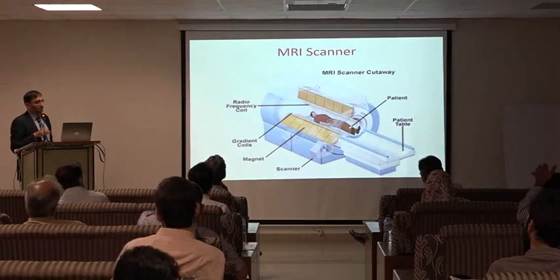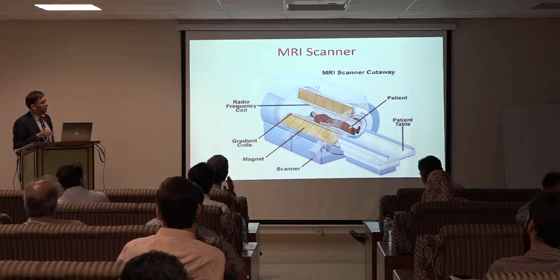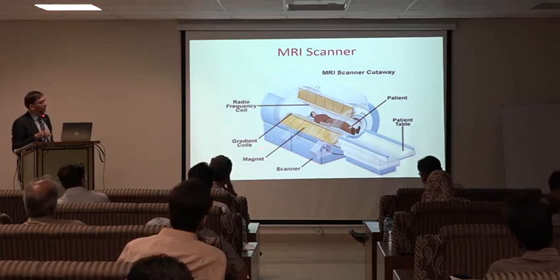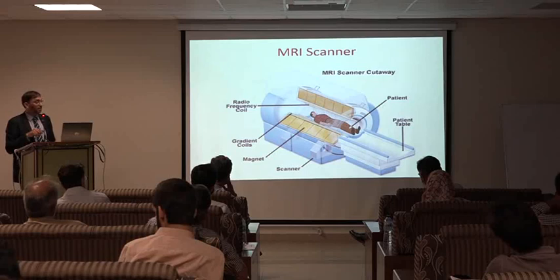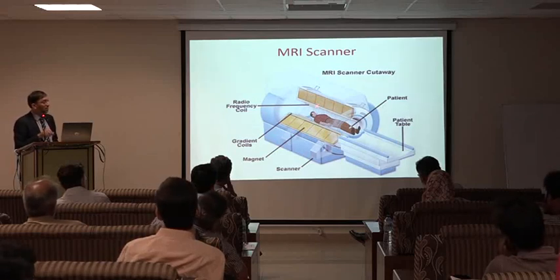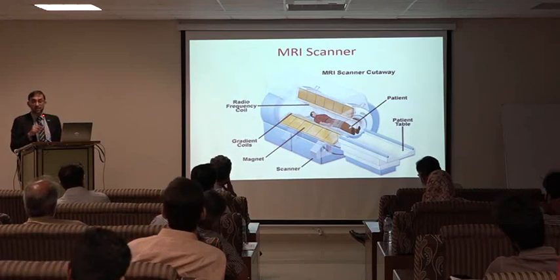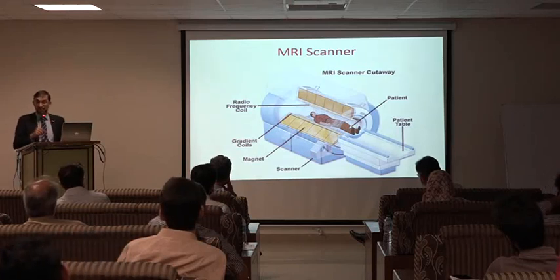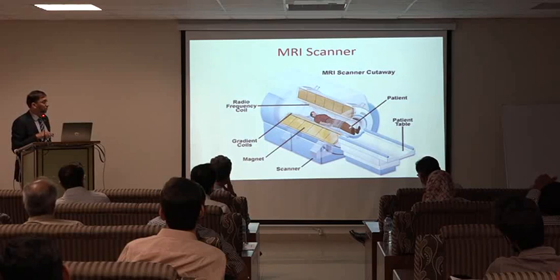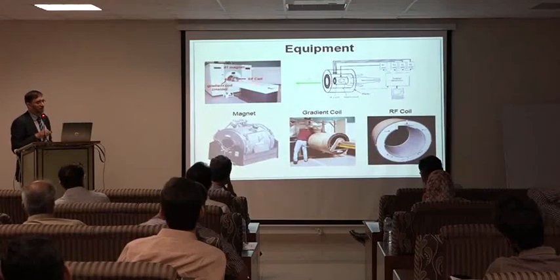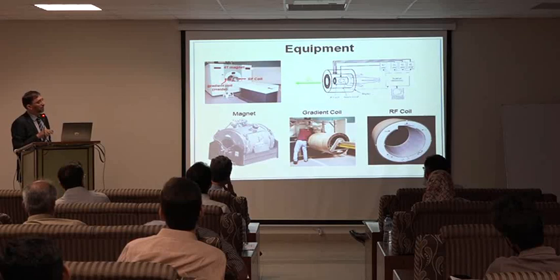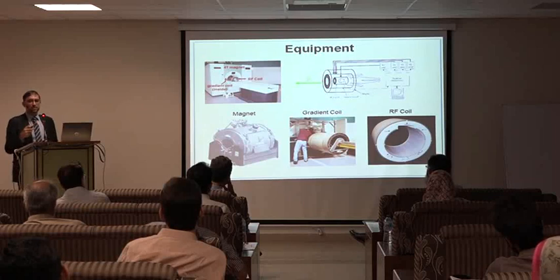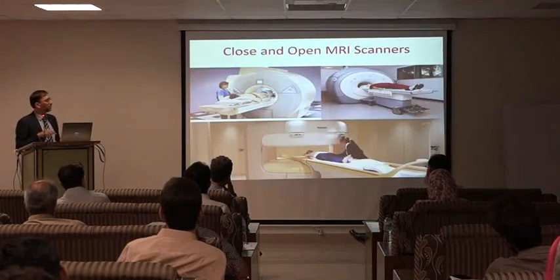This is how the MRI scanner looks like. These are the radio frequency coils and the gradient coils. I said that there are 3 types of gradient coil. The patient is lying there, and it's actually in these gradient coils that 600 ampere or even more amount of current is passing through. So it's actually huge. This is the equipment of MRI. This is the small animal scanner which is shown here, but these are the gradient coils, RF coils, transmitter coils, receiver coils, and so on.